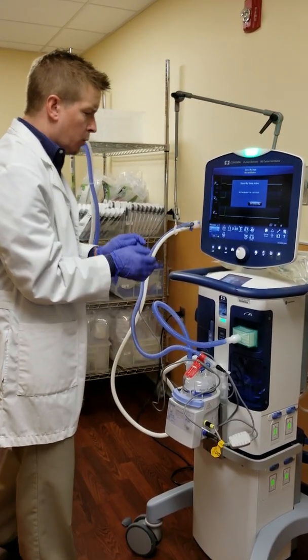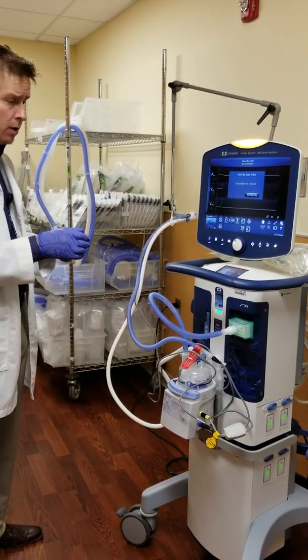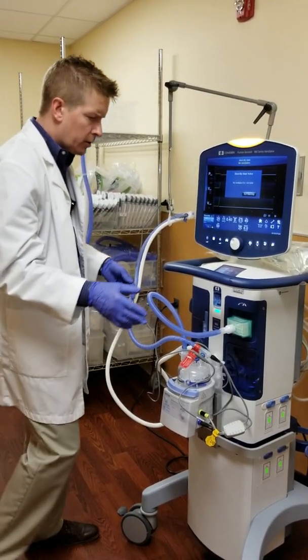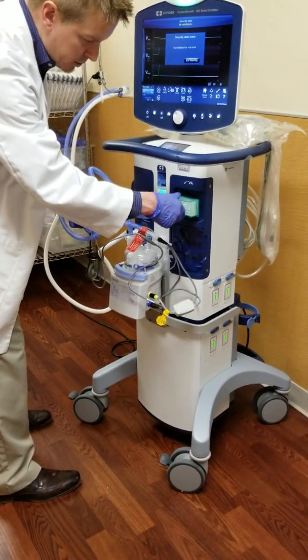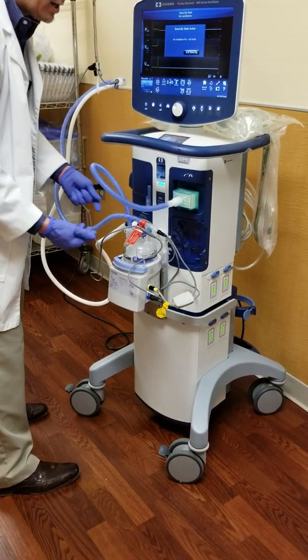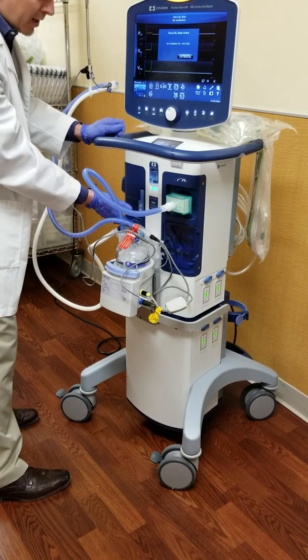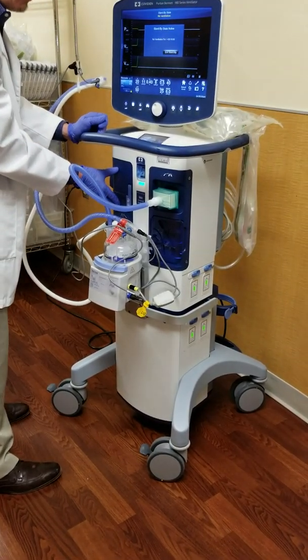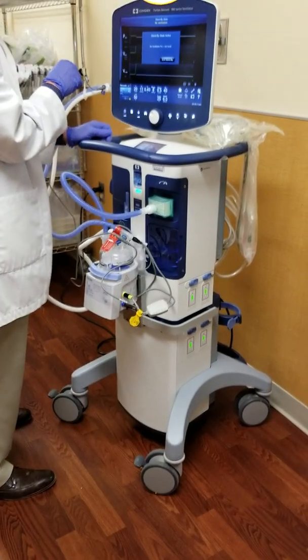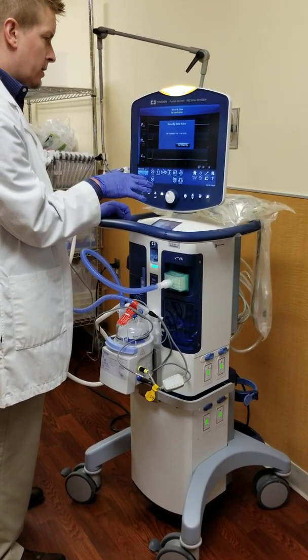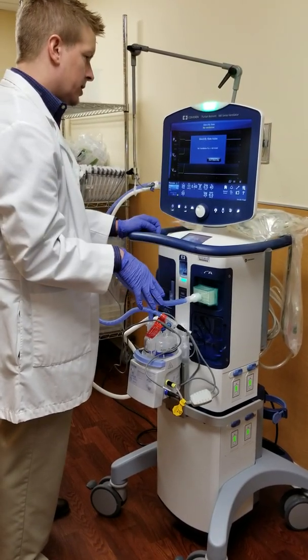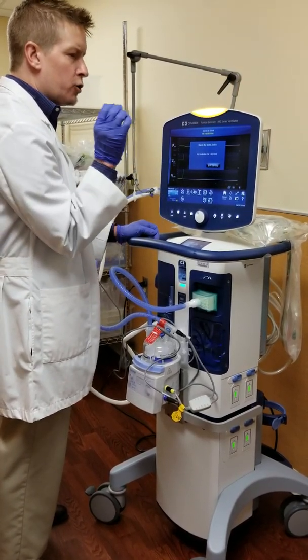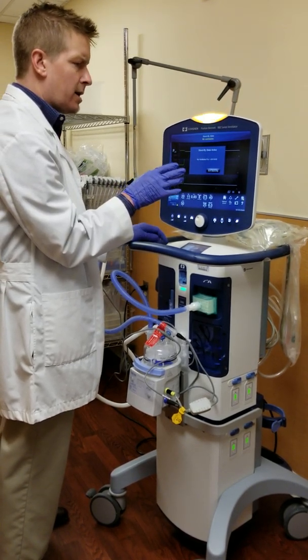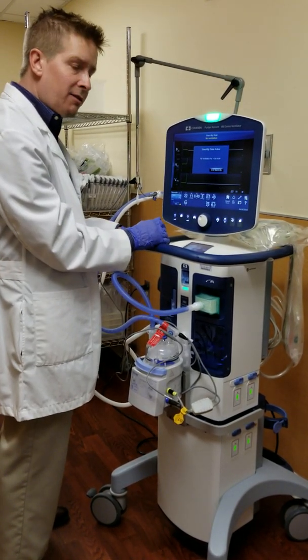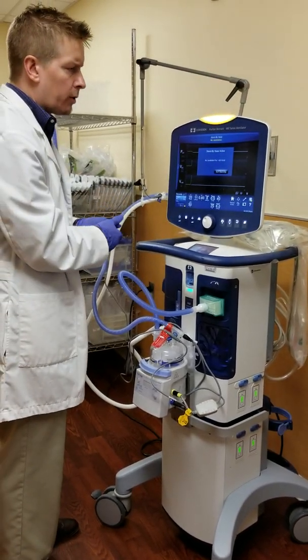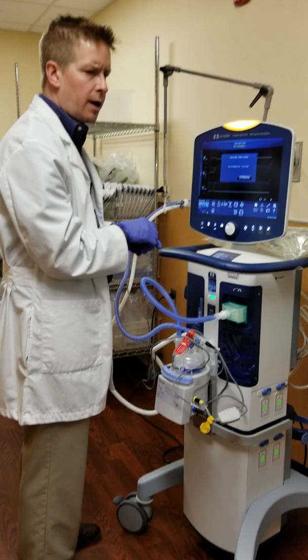But for now, what you're going to do, if you have to use this for a neonatal intervention, what you're going to do is you're going to put the neonatal circuit on it with 2 adapters on the inspiratory and expiratory limb. You're going to change the filter to a neonatal filter. You're going to change the door to a neonatal door. Run an SST as the neonatal circuit is applied. Follow the directions. Use CPAP and or pressure SIMV if you need a drive pressure. And if the baby is intubated, obviously for our region, we lean more towards a pressure SIMV.